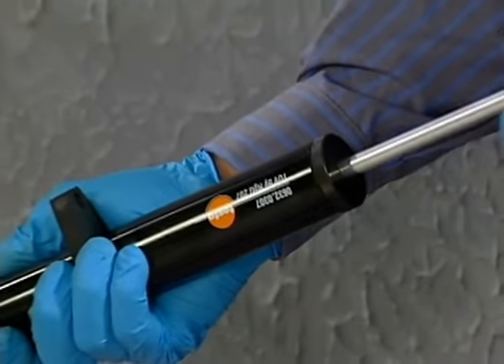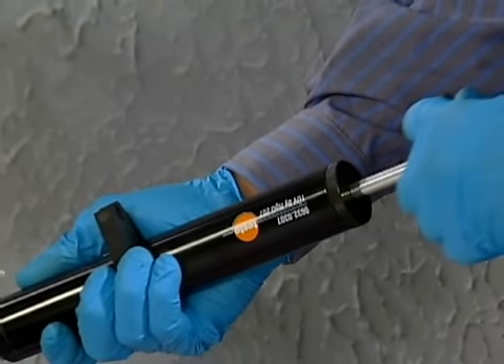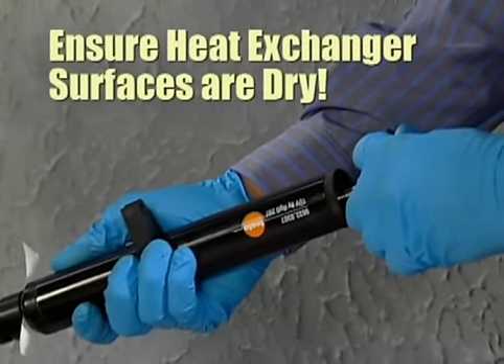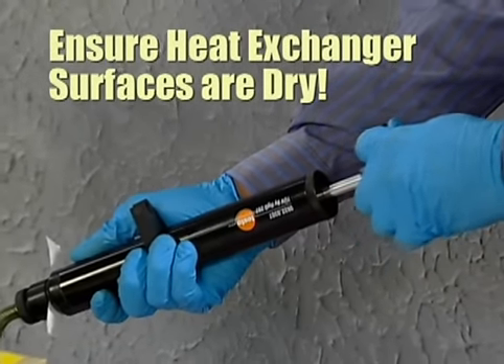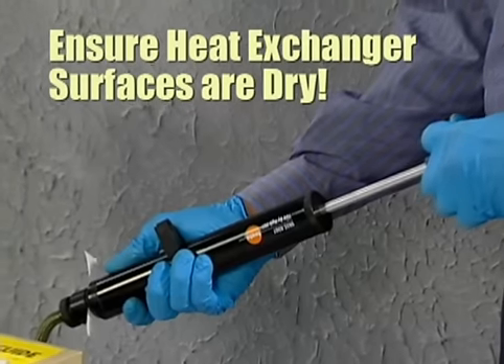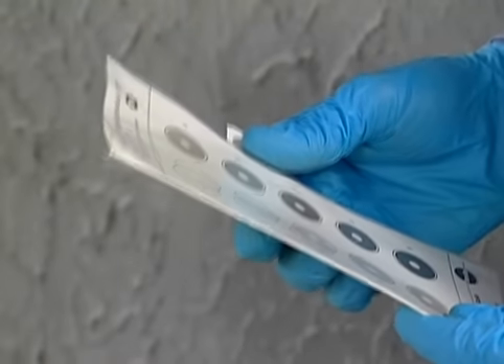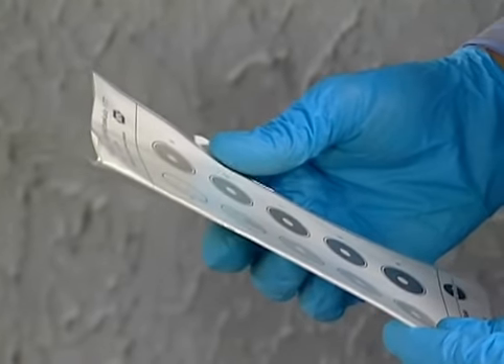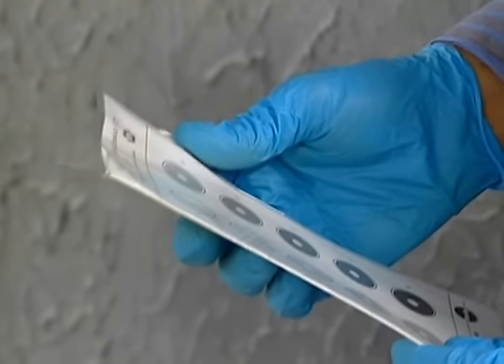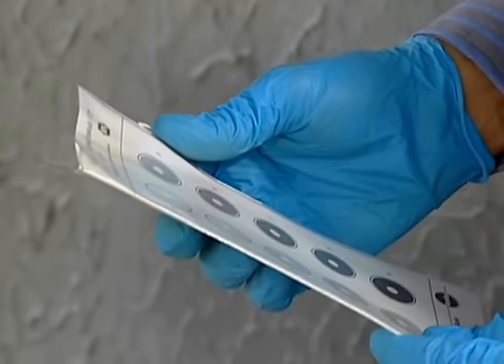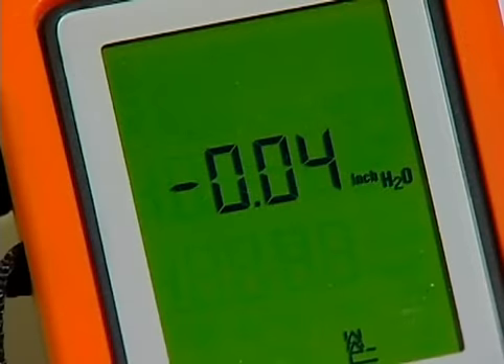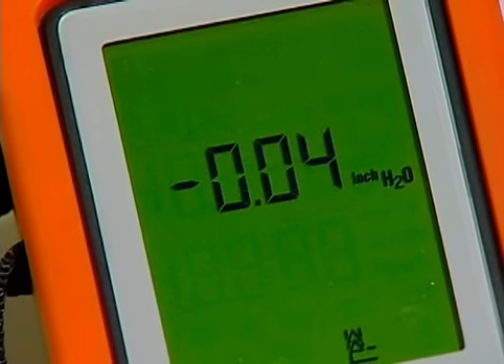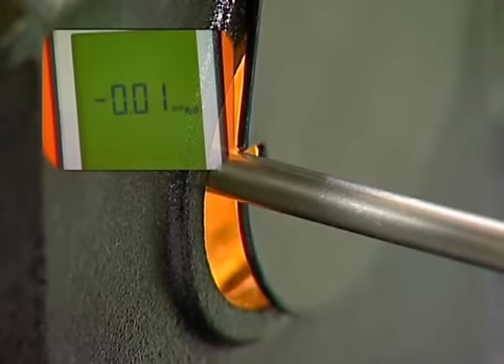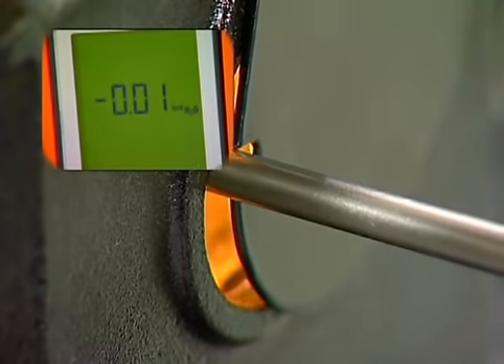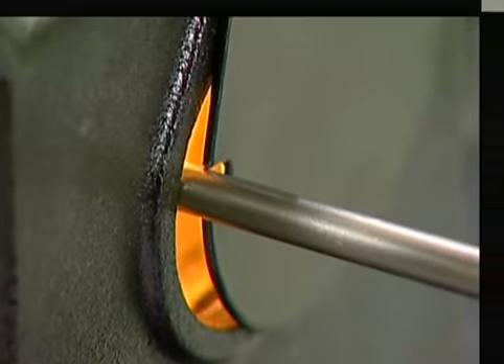If the burner has not been in operation for some time, it's important to perform a quick fire test to ensure that the heat exchanger surfaces are thoroughly dry. Run the unit for at least 5 minutes. Perform a smoke test and ensure that the unit is functioning properly. Note any problems so that you can repair them during the tune-up. Check the draft drop by testing at the breech and over the fire. If the drop is greater than 0.04 inches, there's probably a buildup of soot and scale, or you may have air leaks in the unit.